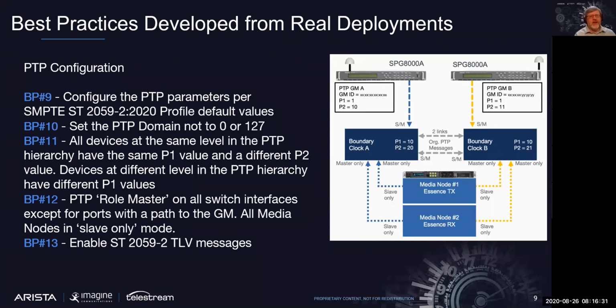We've seen through some interops and field deployments that there have been issues with some implementations around management messages. Our recommendation is that it's better during your commissioning phase to work out issues you may have in your devices or topology, fix that during commissioning, and then in the future it's very easy to turn it on.